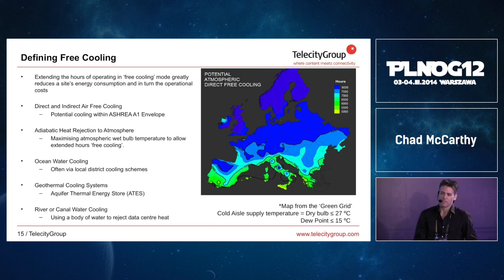So that means that you have to filter the air, which is a little bit limiting. The definition of a filter is that it has holes in it, otherwise no air gets through. And if you have a very fine filter, then you'll spend more fan energy pressing the air through the filter than you would have saved had you had a mechanical system. So the filtering is really limited to anti-pollen measures, to things like pollen and larger particles, which means that you have a certain amount of ingress from whatever is outside to inside.